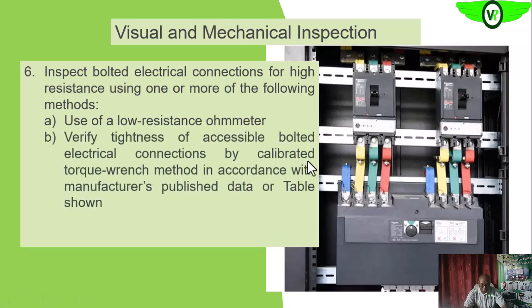Okay, so we can use the torque wrench, a calibrated torque wrench, to tighten those bolts to see that the appropriate torque is applied to those bolts. Then we can also perform a thermographic survey. During the thermographic survey, you would have allowed the equipment to be loaded for some time, that is, in operation for some time, so that all of these conducting bars would have been heated up by the flowing current. Okay, we'll load them as much as we can. Then we'll take the thermographic survey to be sure that we do not have any hot spots on the circuitry.